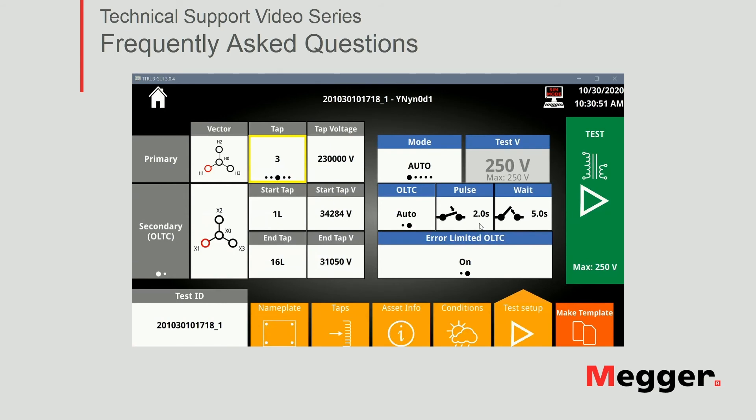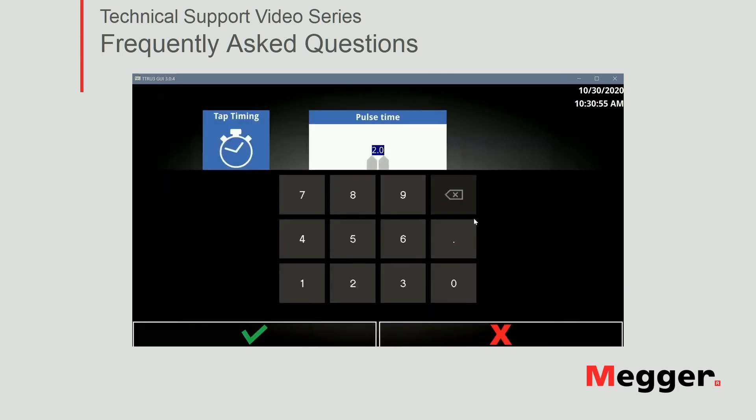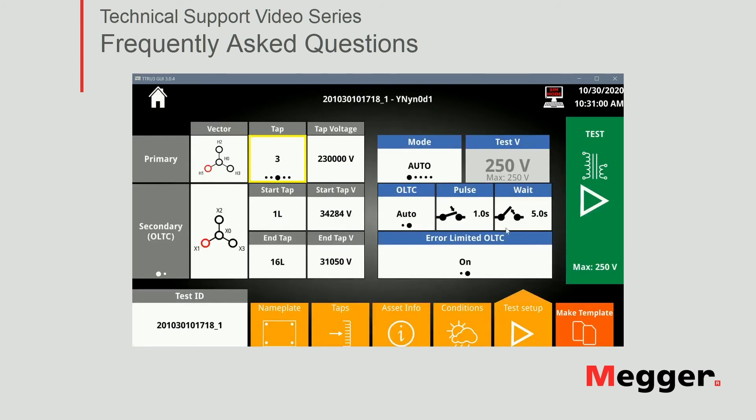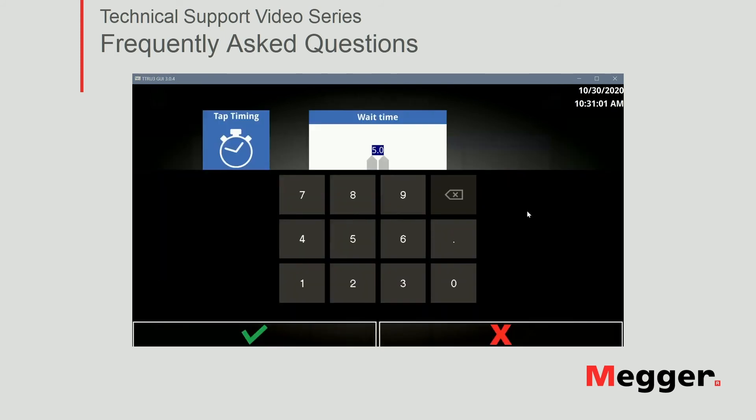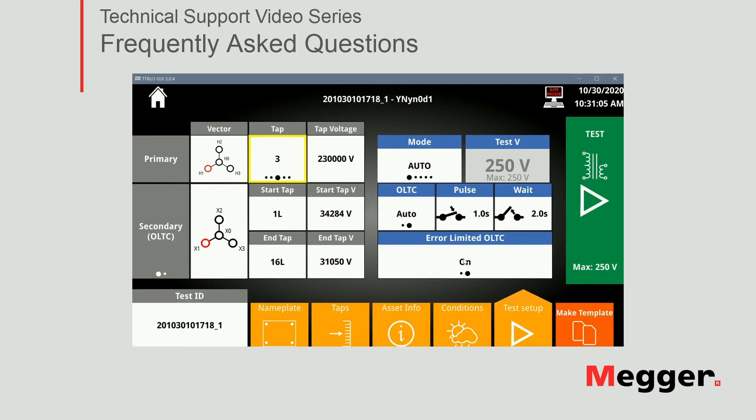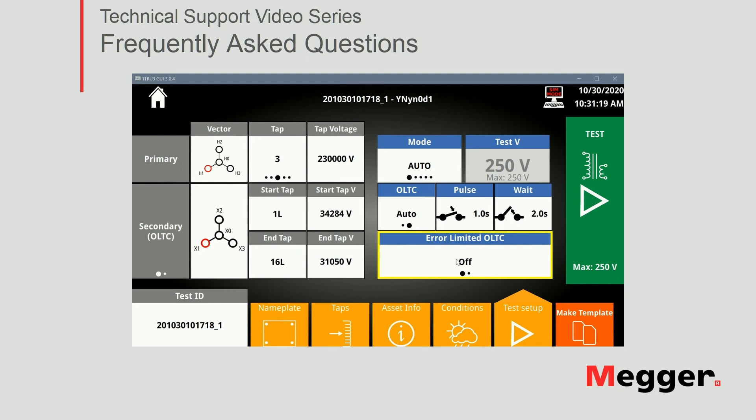So I'm going to leave, I'm going to change it to one second to make it faster. We remember we are running simulation and just two seconds for the wait times, just to make it a little bit faster. And I'm going to disable the error limited OLTC because that would stop my test in case any result is out of the limit established in the settings of the TTRU3 software. So at this point, we're pretty much ready to start our test.